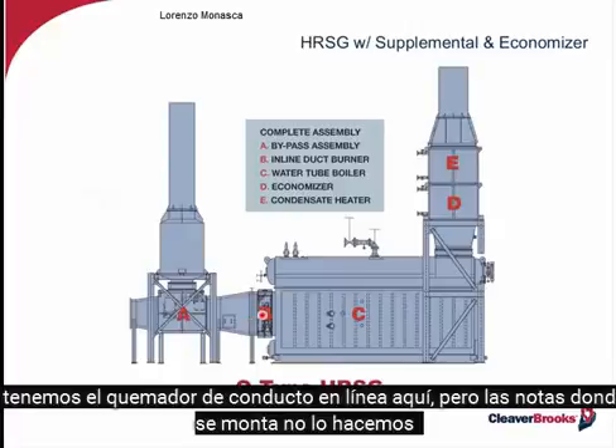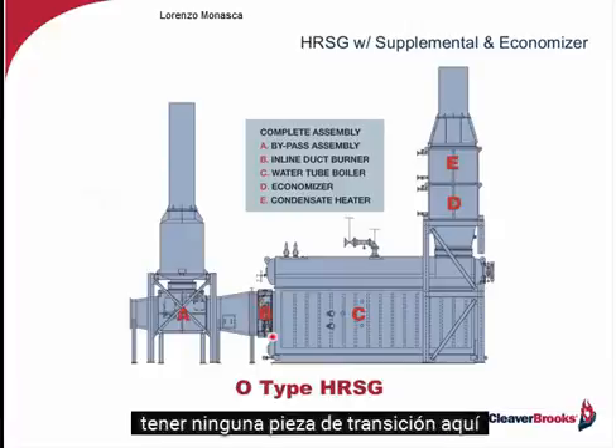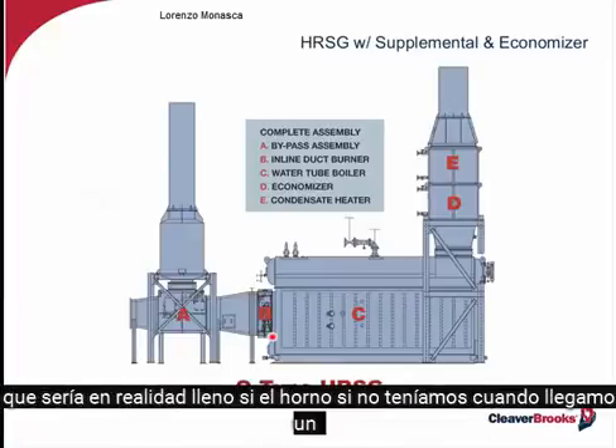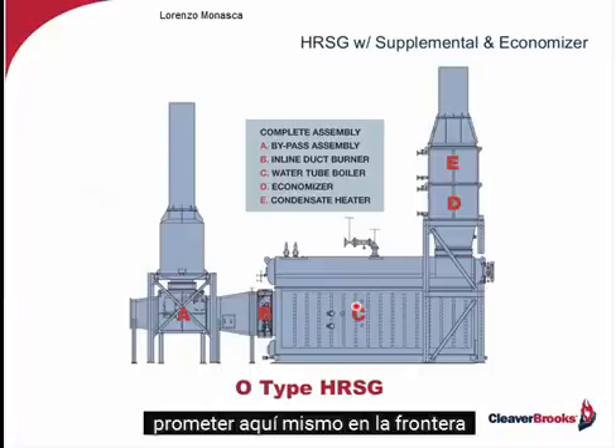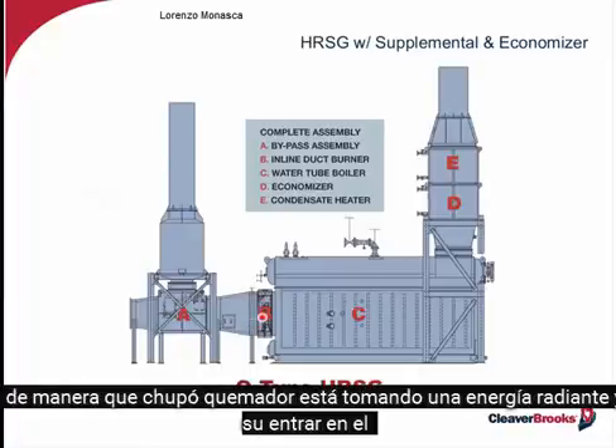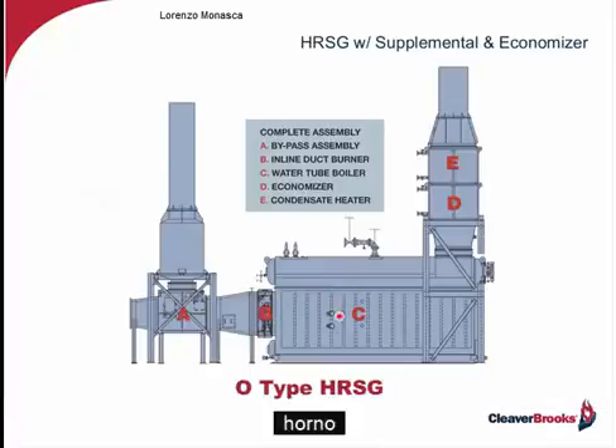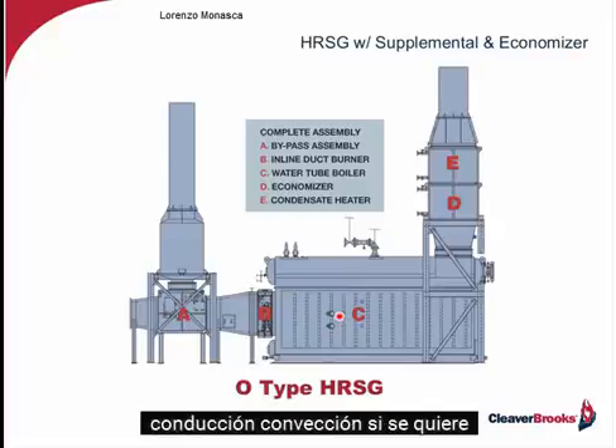We've got the inline duct burner right here, but notice where it's mounted. We don't have any transition piece here, which would actually act as a furnace if we didn't have one. We've got a furnace right here in the boiler. So that duct burner is now taking that radiant energy and it's going into the furnace, and we're generating steam through radiant energy or radiant conduction convection, if you will.